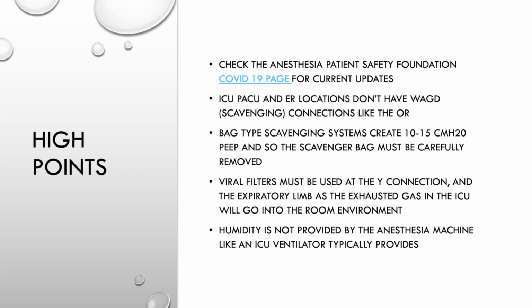Viral filters also have to be used at the Y connection and the expiratory limb, as the exhausted gases will be going into the room, into the ICU or the ER, the PACU. And because they go into the room environment, we want to filter the viral particles as well. Humidity is not provided by the anesthesia machine like an ICU ventilator, so you'll typically have to account for that in the use in the ICU.